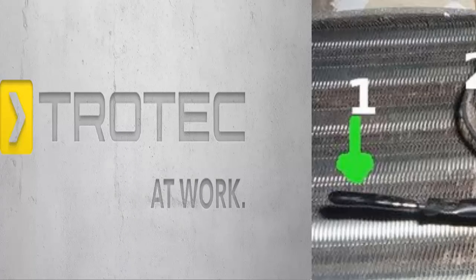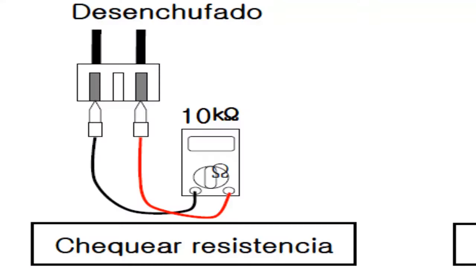For the Trotec brand, Error E3 is due to an issue with the evaporator's temperature sensor. For problems with the temperature sensor, it is recommended to disconnect it and measure its resistance with a multimeter. Its value should match the one indicated in the manual and should never be infinite.